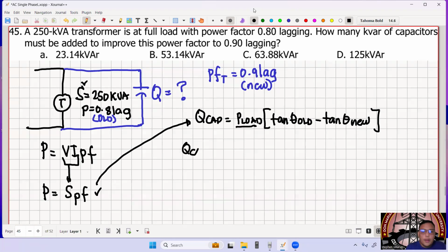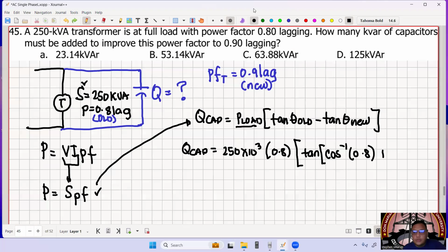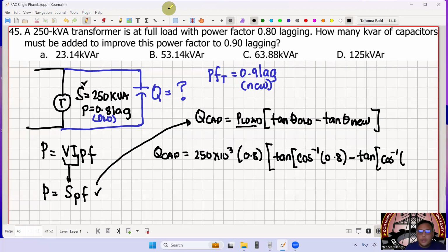Q cap is equal to 250 kilo times power factor of 0.8 multiplied by tangent theta old. So this is arc cosine of 0.8, minus tangent of arc cosine of, since it doesn't fit, let's continue: tangent of arc cosine of 0.9. So 250 kilo times 0.8 times the quantity tangent of arc cosine of 0.8 minus tangent of arc cosine of 0.9.